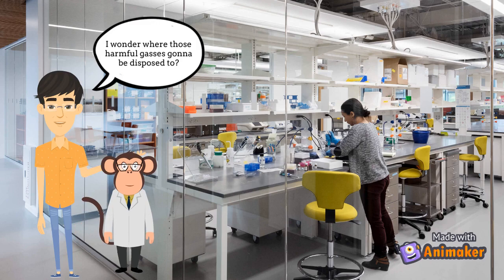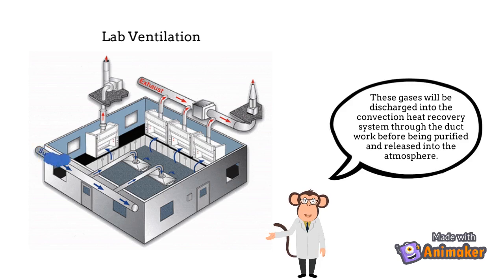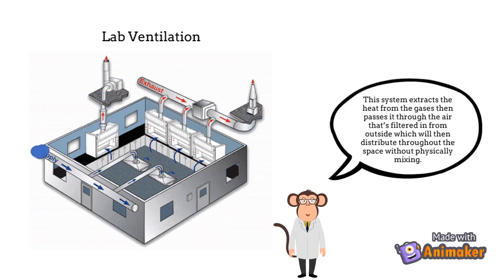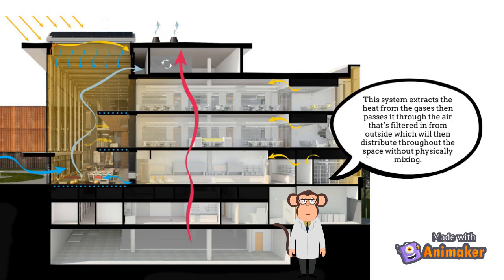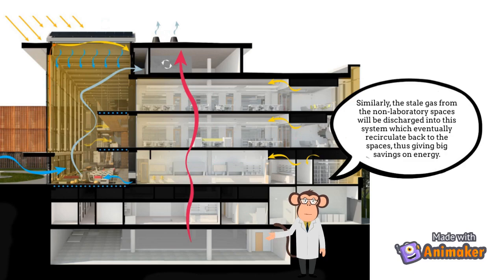I wonder where those harmful gases are going to be disposed of. These gases will be discharged into the convection heat recovery system through the ductwork before being purified and released into the atmosphere. This system extracts heat from the gases and passes it through air filtered in from outside, which is then distributed throughout the space without physically mixing. Similarly, stale gas from non-laboratory spaces is discharged into the system and eventually recirculated back to the spaces, giving big savings on energy.